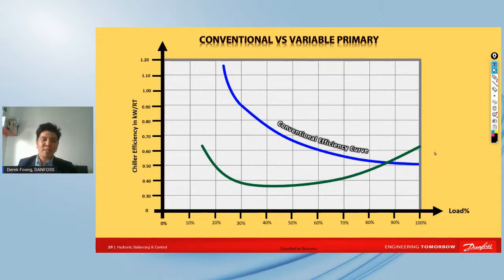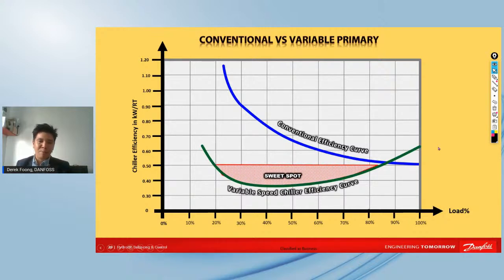So now, it brings us a question: what is the best fitted variable speed compressor system? And the load is always varying, right? So to fit the demand to the supply, we also need to regulate the compressor speed in the chillers. So variable speed chillers have come into the picture for the last decade, and in these last 7 years they have become increasingly popular. And these chillers have sweet spots, meaning that if they operate within a certain load range, they will be operating at a certain efficiency.